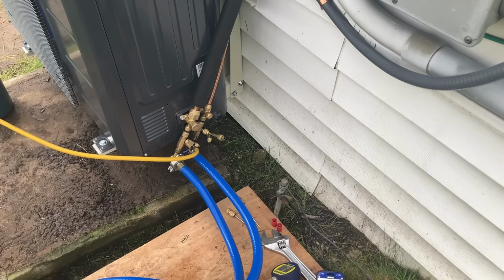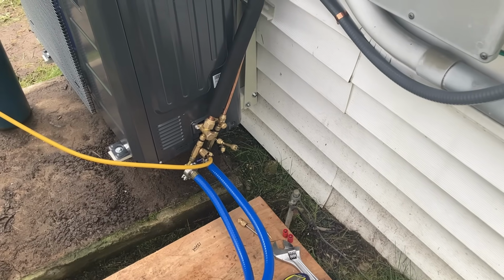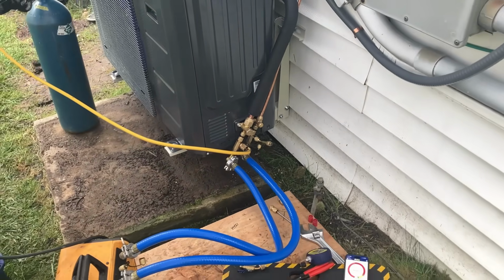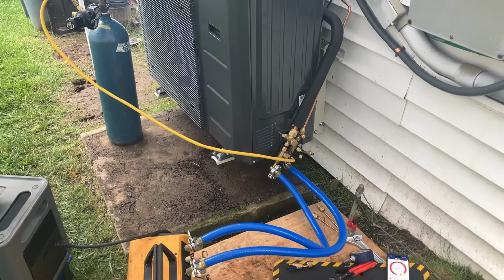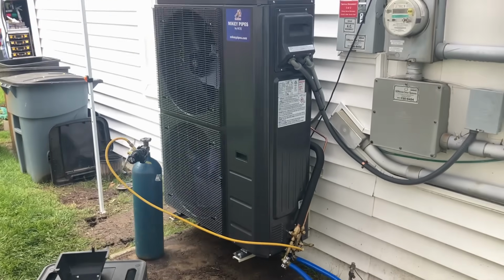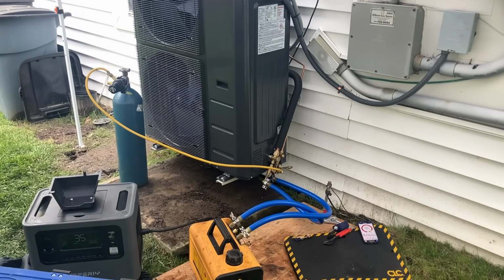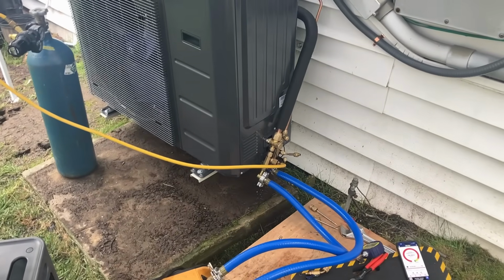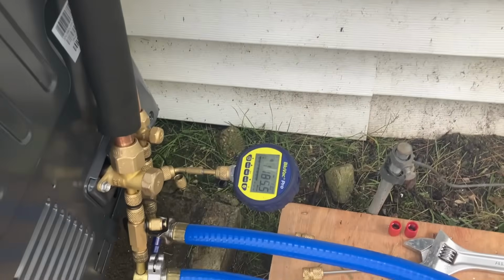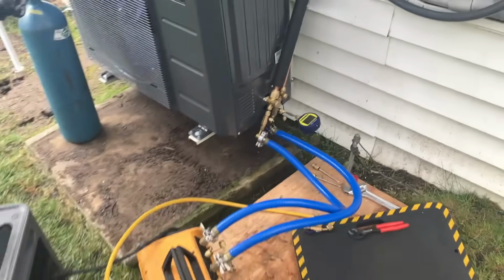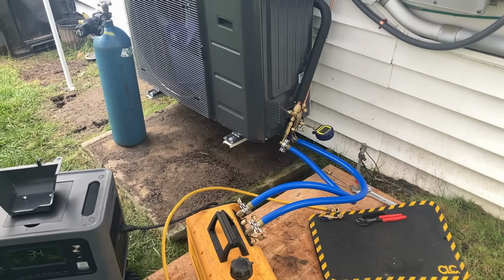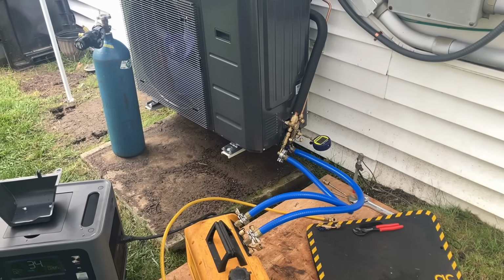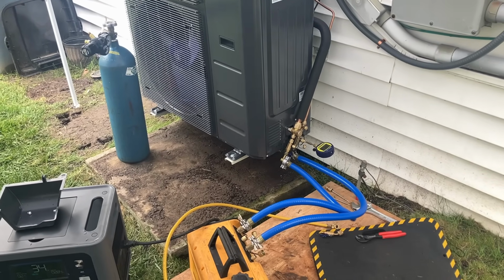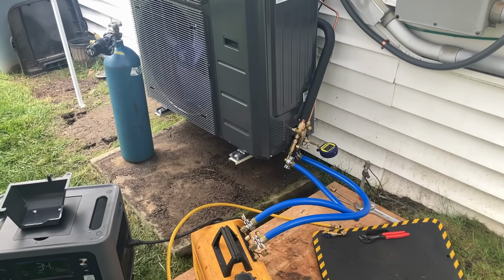It's upsetting, but unfortunately it is what it is. Let's see if we can force out whatever is causing the leak here and make the problem go away. Because I need to have a nice, tight and dry system. My customers pay for quality, leaving no stone unturned, and I'll be damned if I cheat during the final parts of the startup and commissioning of a system. Not happening. All right, we're going to vacuum down this one more time, and I'm going to keep it real. It's going to hold this time. Otherwise, I'm dumping the charge. No, I'm just joking, but this is the 4th nitrogen purge, and it holds a nitrogen test. So I don't know what gives. Maybe the micron gauge is wonky, but let's go see what Daniel and Peter did in the attic. All right, let's go see.